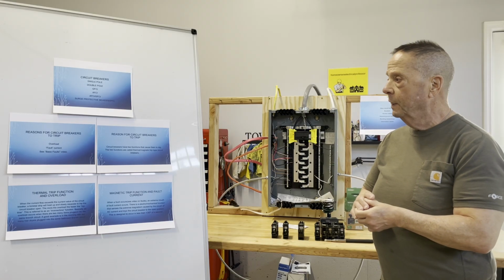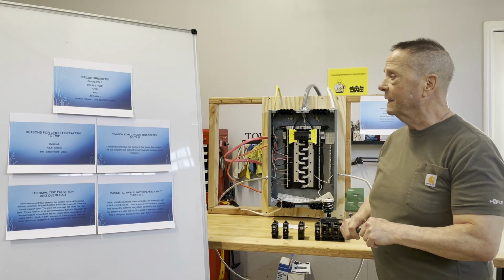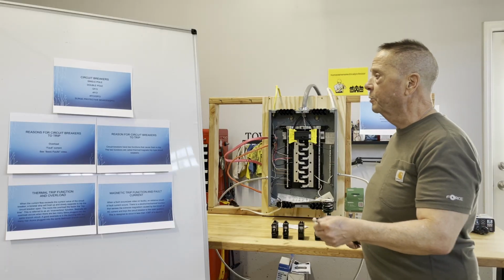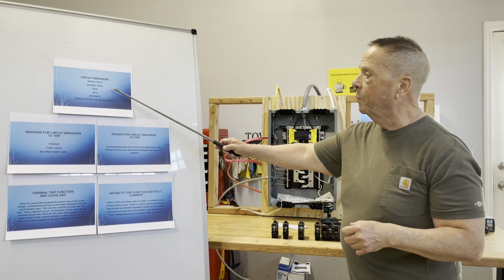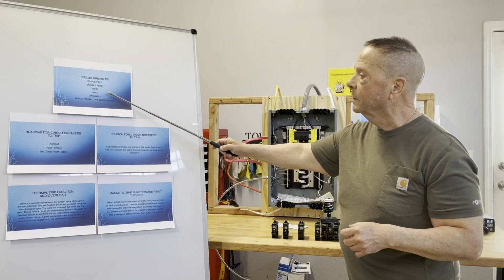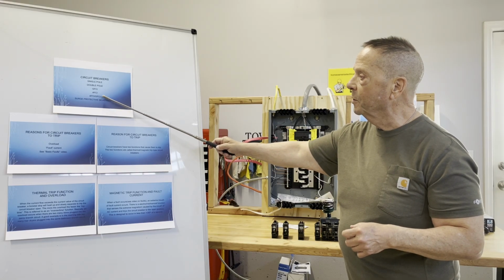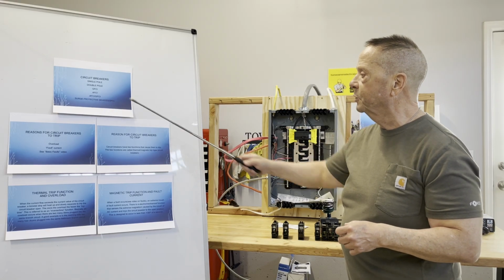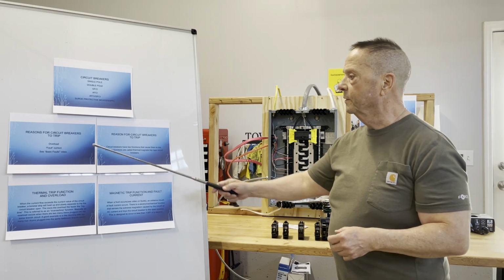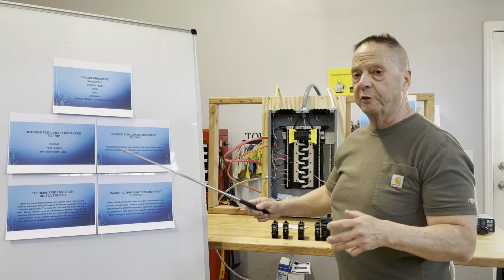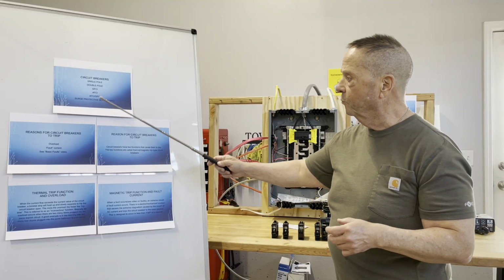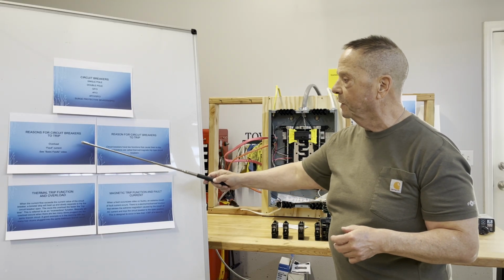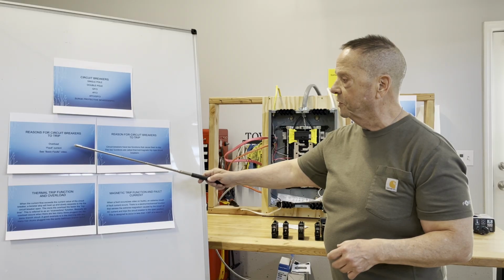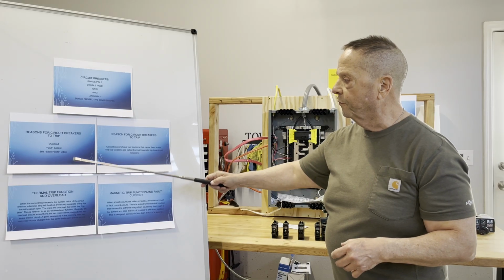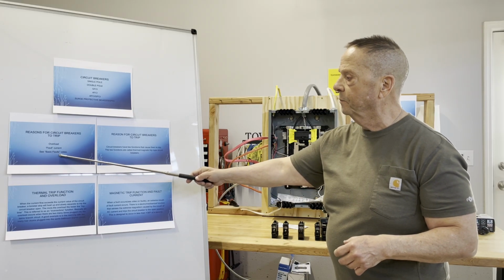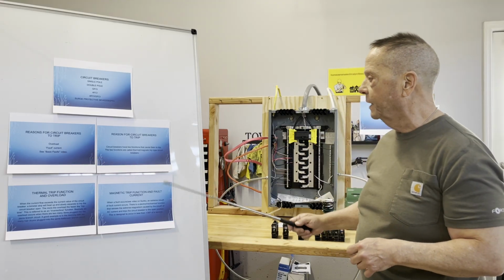In this episode, we're going to start talking about some circuit breakers, okay? A little more detail. You basically have single pole, double pole, ground fault, arc fault, combination arc fault and ground fault, and then we have surge protective devices. Circuit breakers are there to protect the wire, okay, and with the case of ground fault, to protect humans. There's basically two reasons they trip: an overload or fault current. I have a video on basic faults, okay.